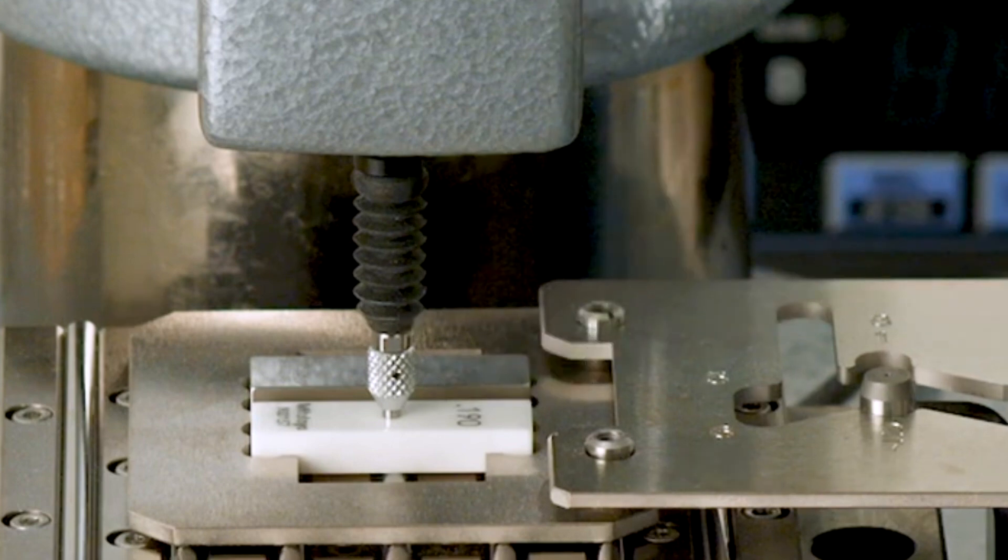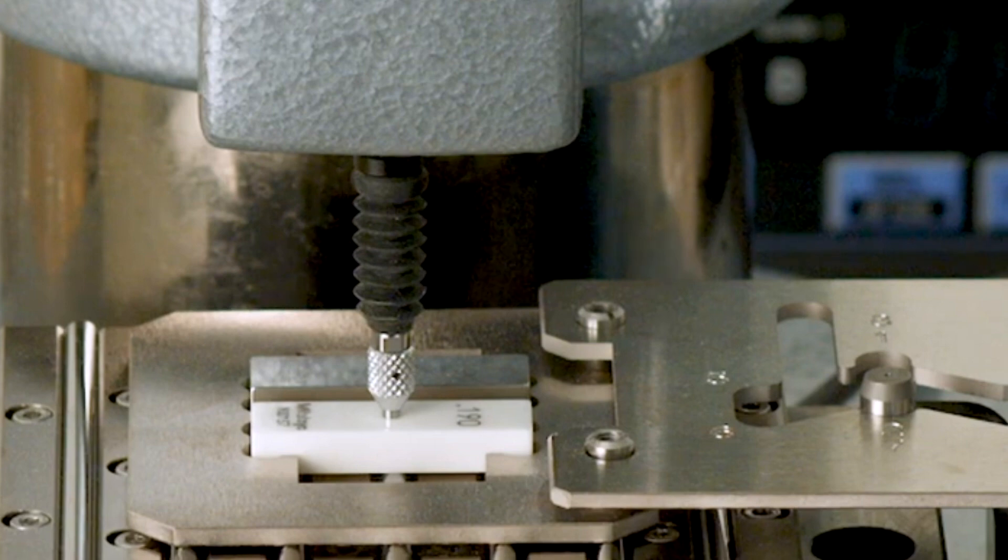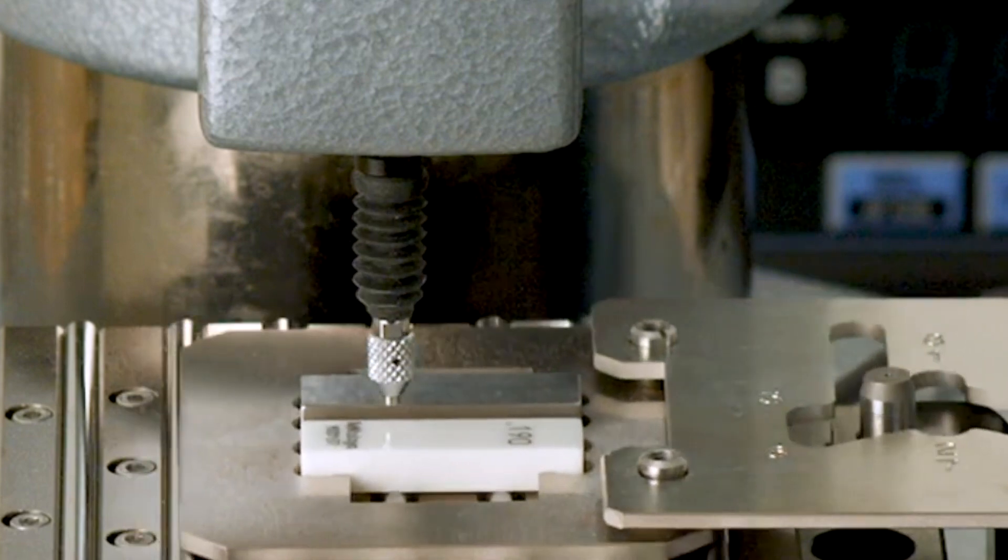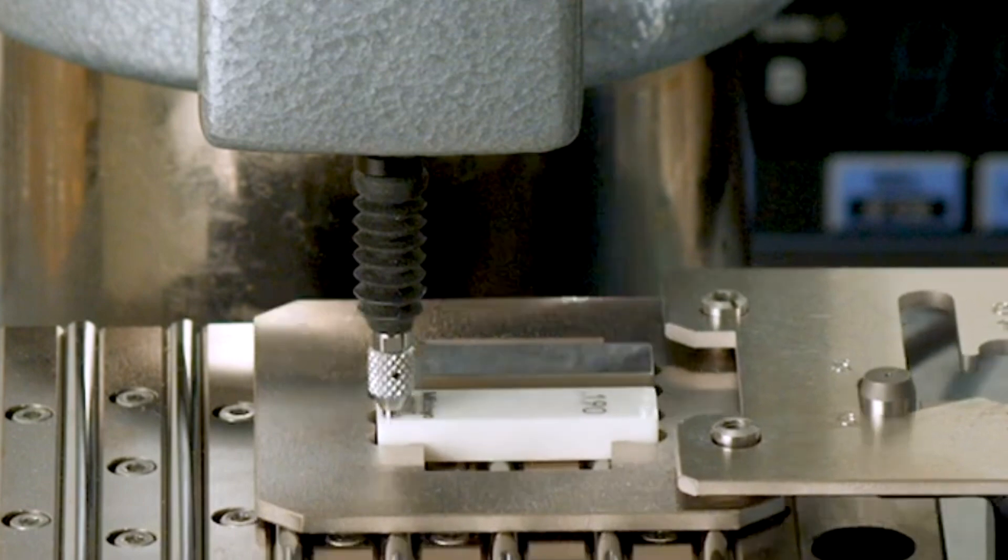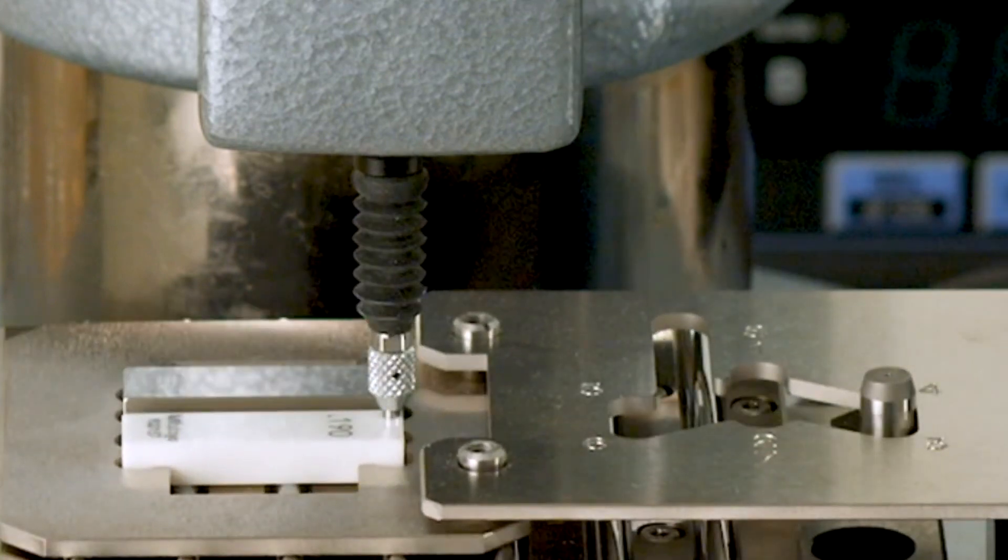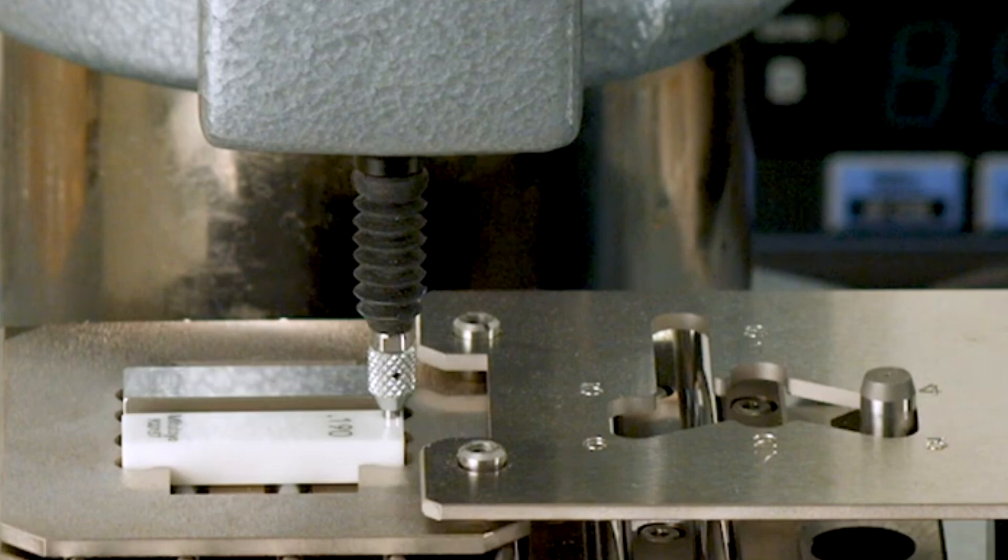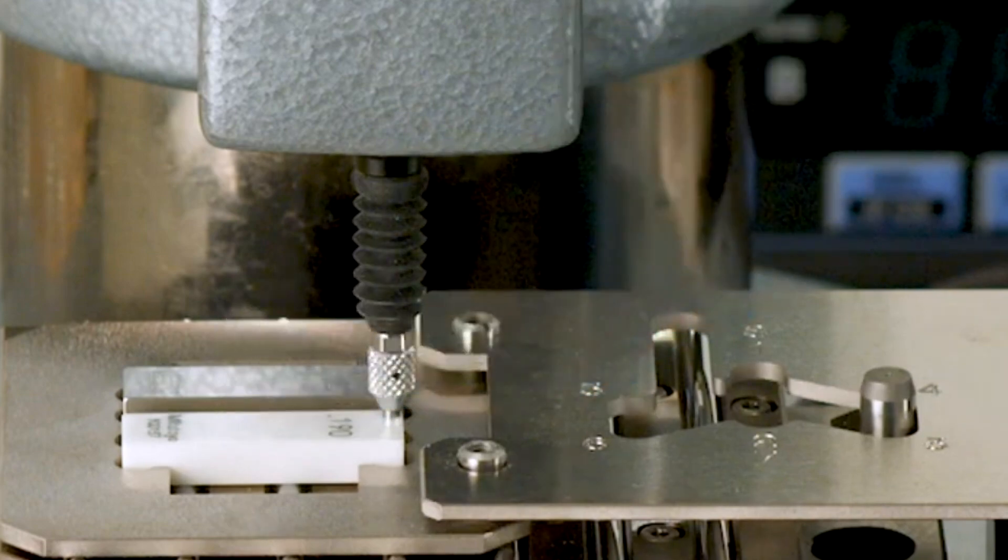And the standard discusses the importance of checking the size in addition to the gauge point at all four corners. In order to state conformance to grade in accordance to the ASME B89.1.9 standard, all five of these points must be in tolerance.